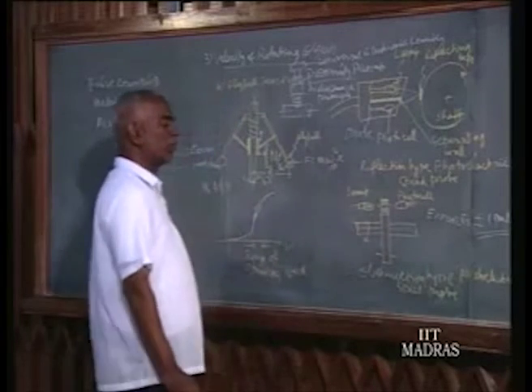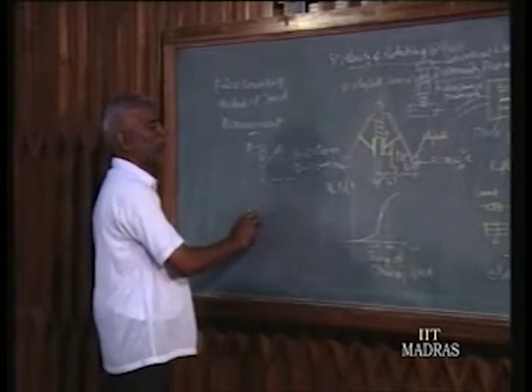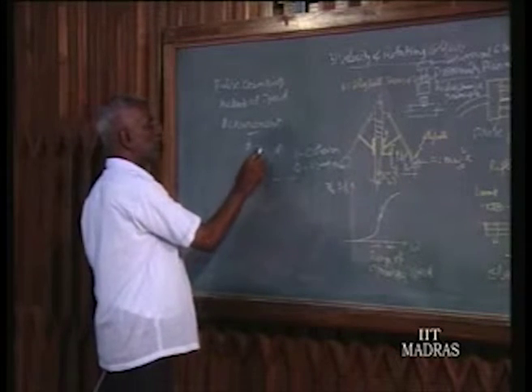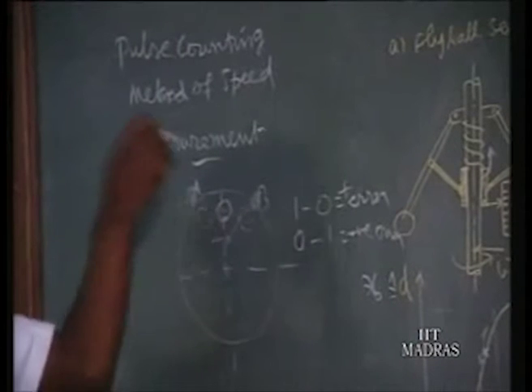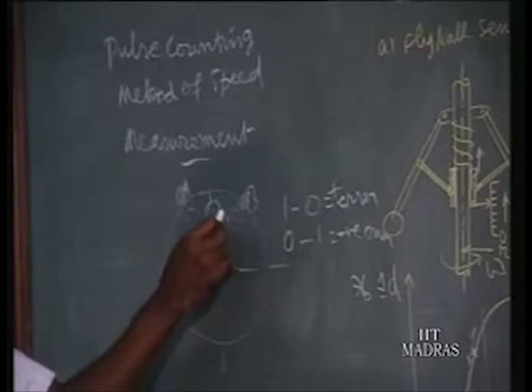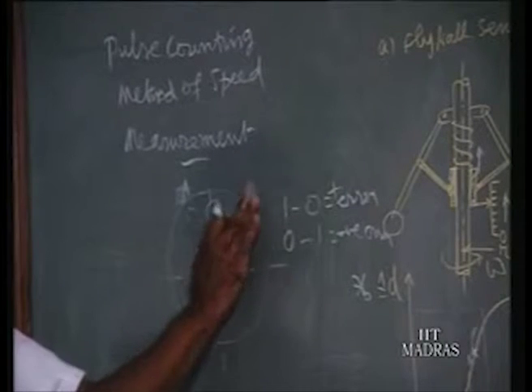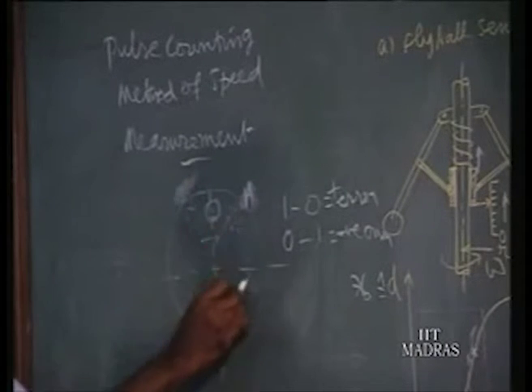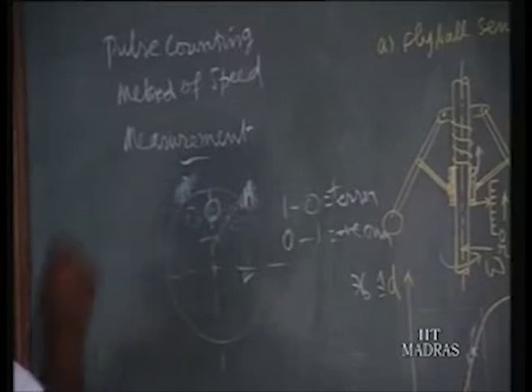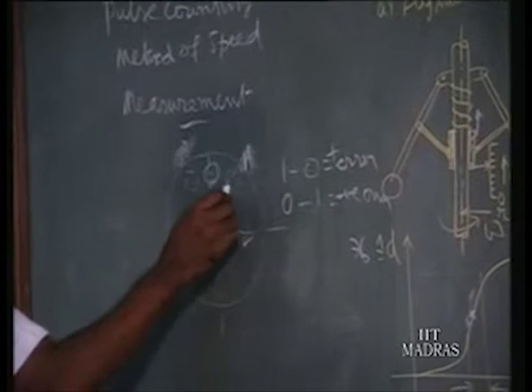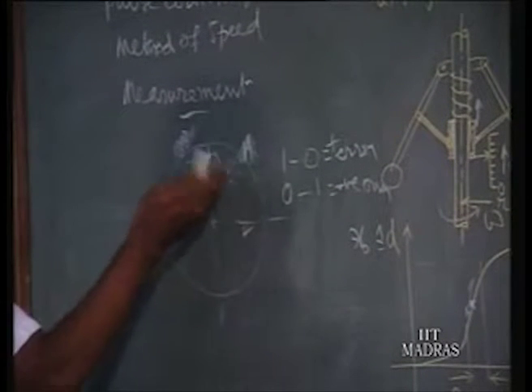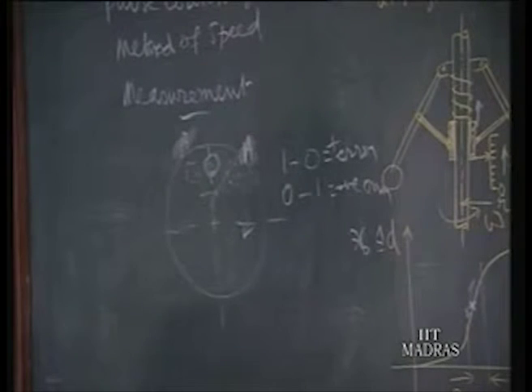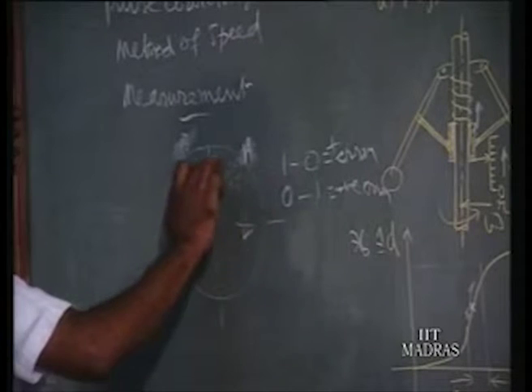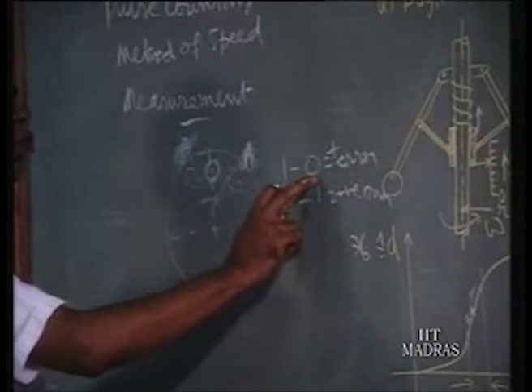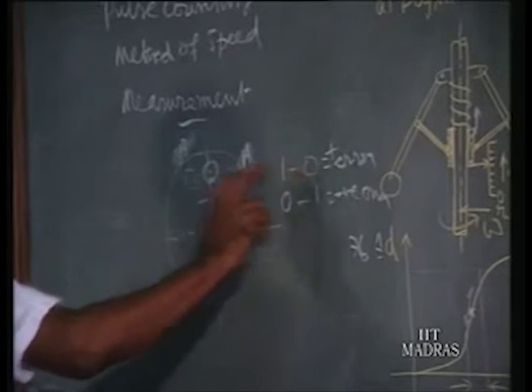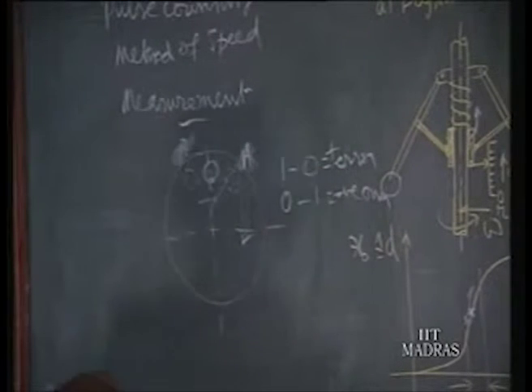And how do we say plus or minus 1 pulse? Just see here as an example. Consider the disc where the hole is the measuring station. When the hole comes, 1 pulse is produced. Suppose the shaft starts rotating at station A, and comes and stops at station B just before the measuring station. Then it has completed almost 1 rotation, but since at no time was it in front of the measuring station, no pulse is produced. So theoretically it has rotated 1 rotation, but the actual measurement is 0. So the error is 1 minus 0, a plus 1 pulse error.